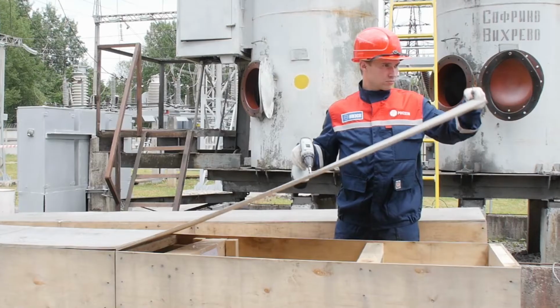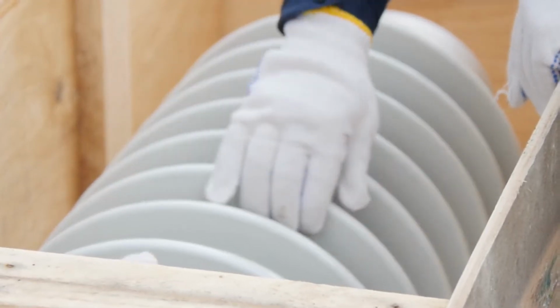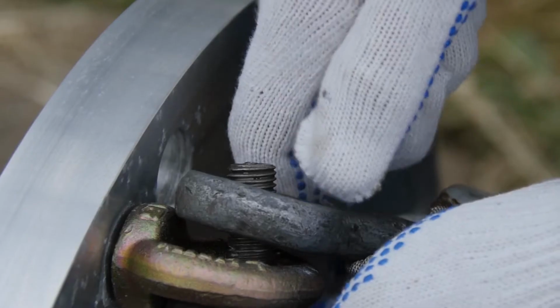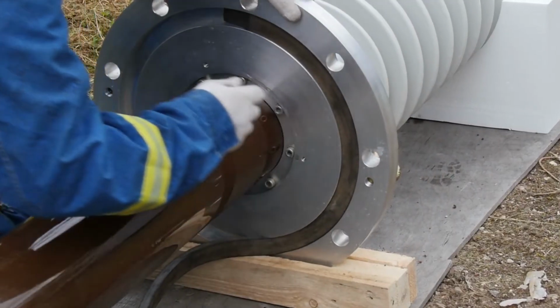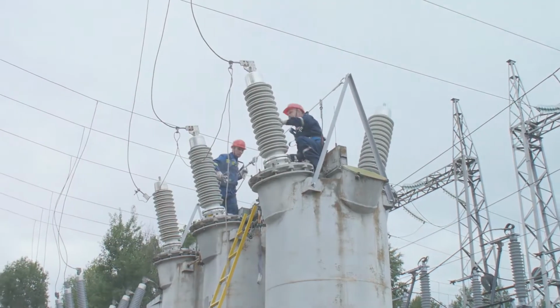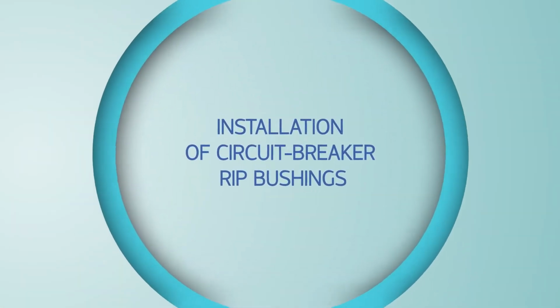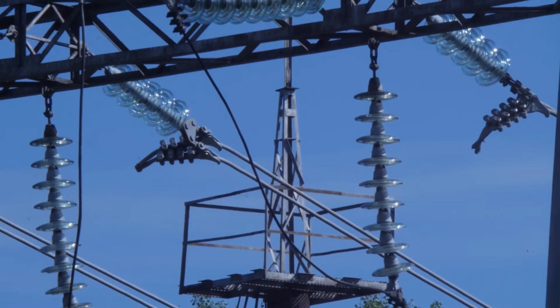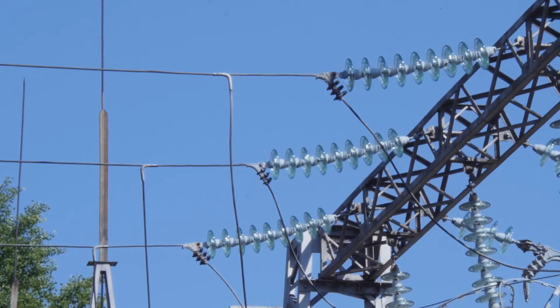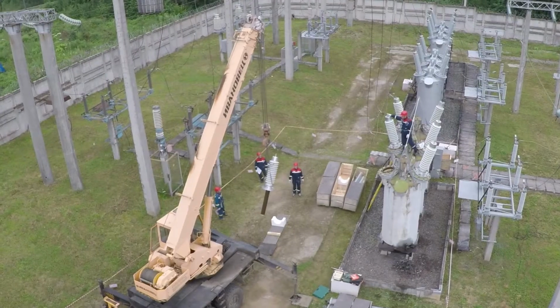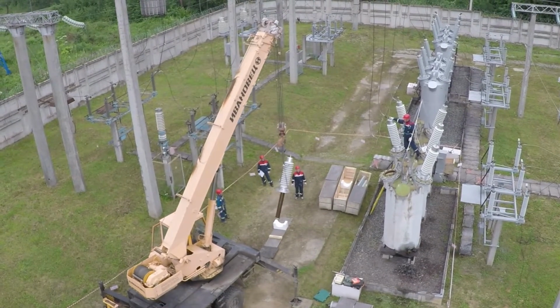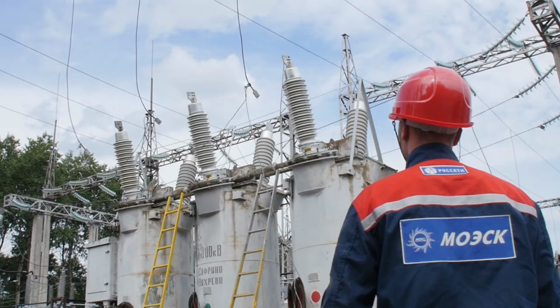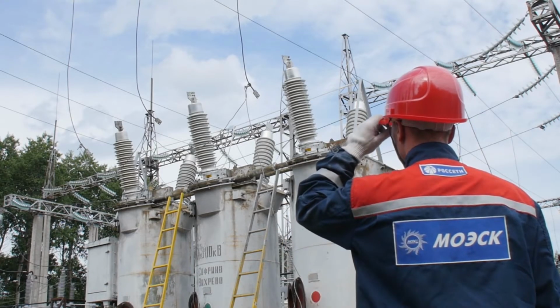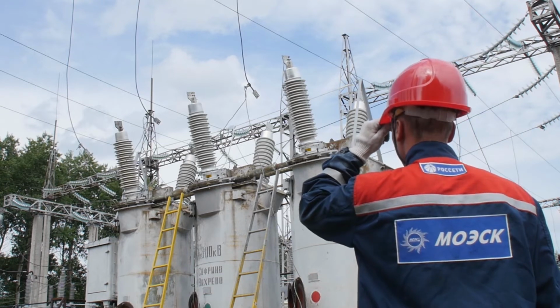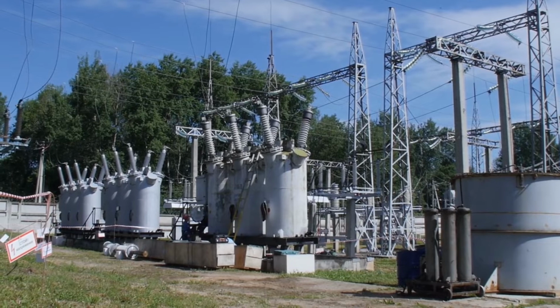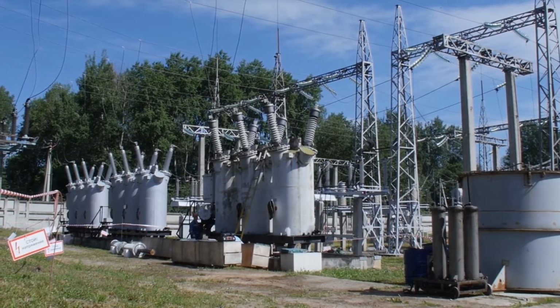This is a video instruction on the installation of different types of Isolator high-voltage RIP bushings. Installation of a circuit breaker RIP bushings. This video part demonstrates a detailed procedure of 110 kilovolt bushings installation on oil circuit breaker carried out by Moscow United Electric Grid Company experts. Installation of external porcelain insulation bushings filled with transformer oil will be shown. Bushings with other types of external insulation are installed in a similar way.